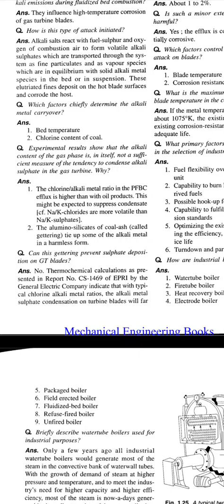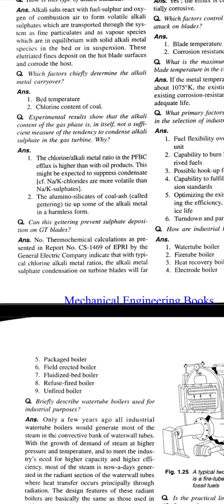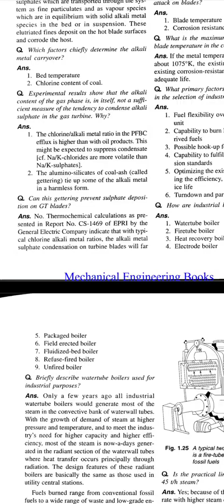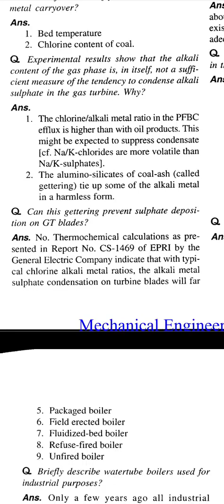Next question: experimental results show that the alkali content of the gas phase is in itself not a sufficient measure of the tendency to condense alkali sulfate in the gas turbine. Why? Answer: the chlorine to alkali metal ratio in the PFBC efflux is higher than with oil products. This might be expected to suppress condensate. NaK chlorides are more volatile than NaK sulfates.